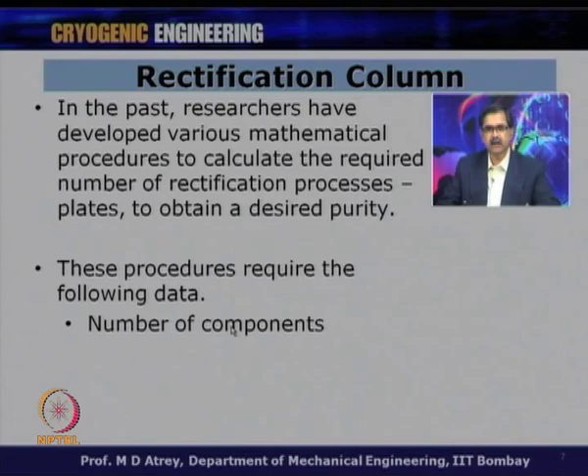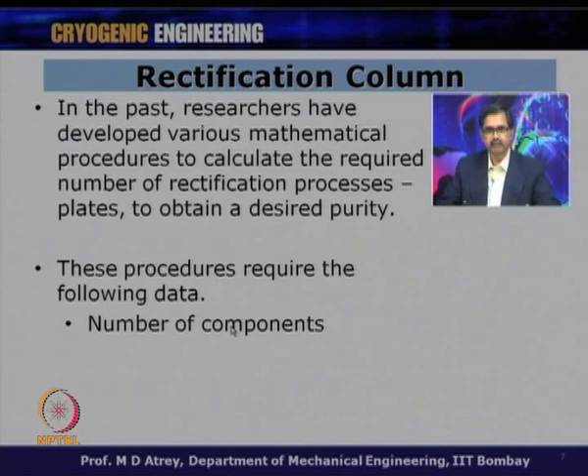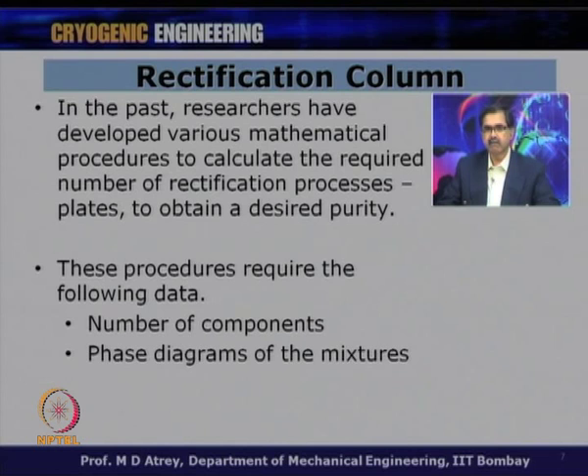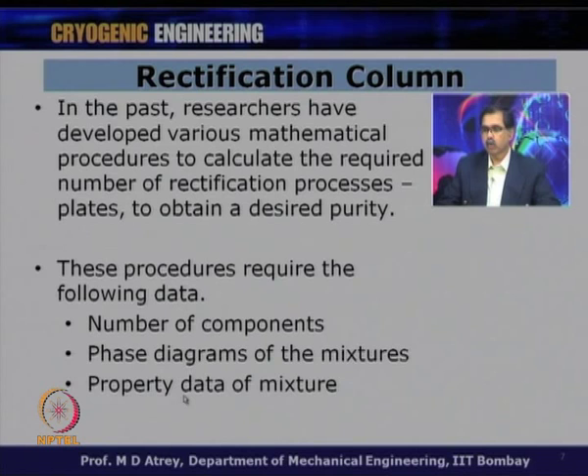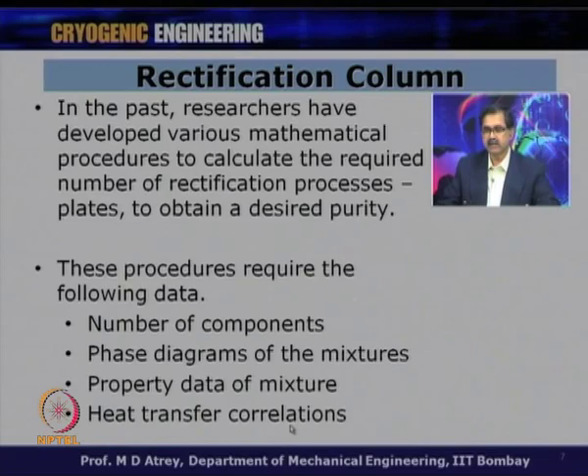These design procedures require the following data: the number of components in the feed (more components make separation and calculation more difficult, requiring a phase diagram of the mixture), property data of the mixture at low temperatures (which is very difficult to obtain), and validated heat transfer correlations for boiling and condensation occurring on every plate.